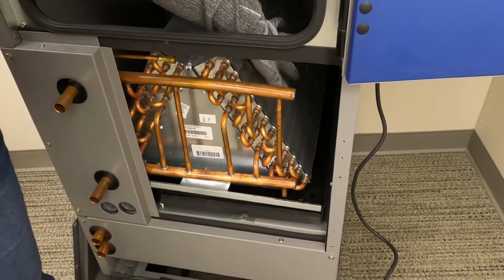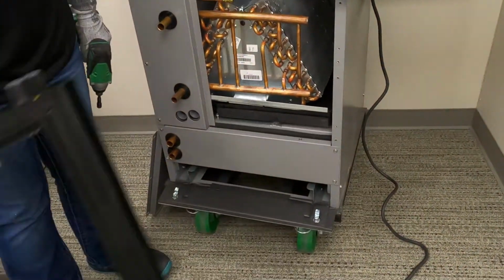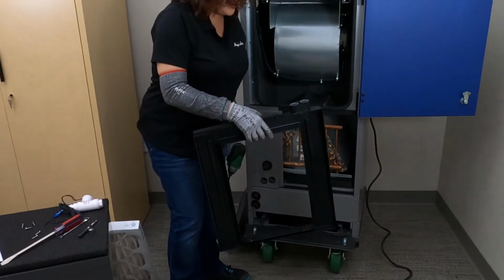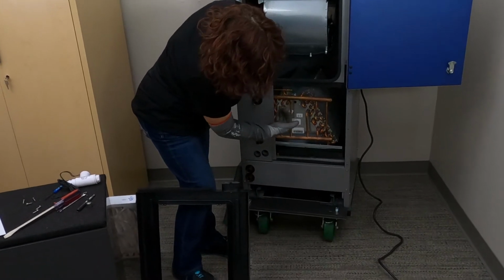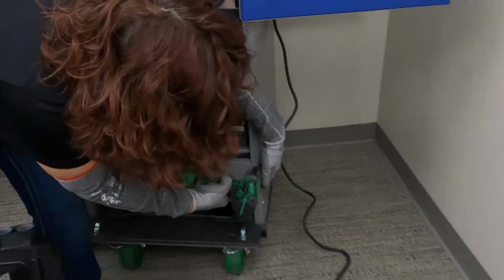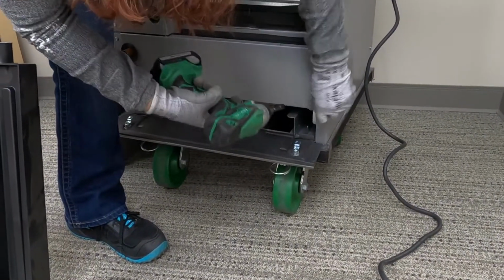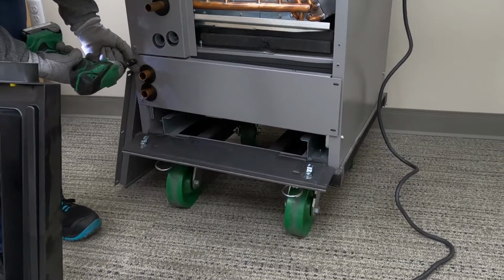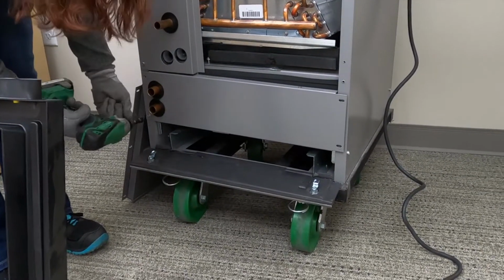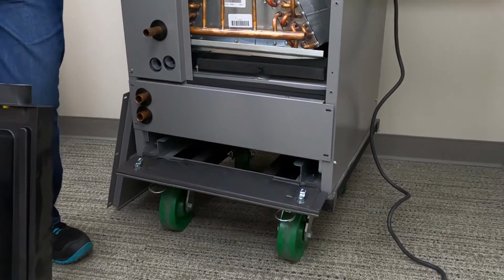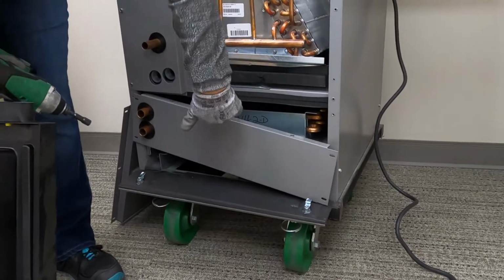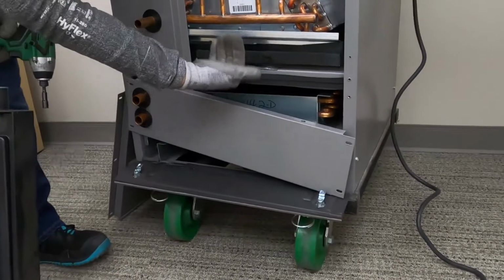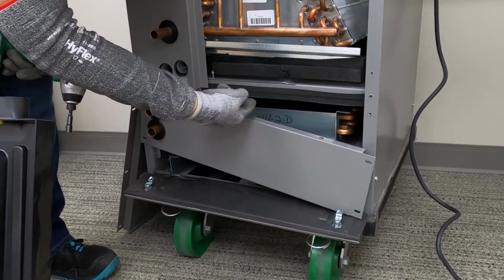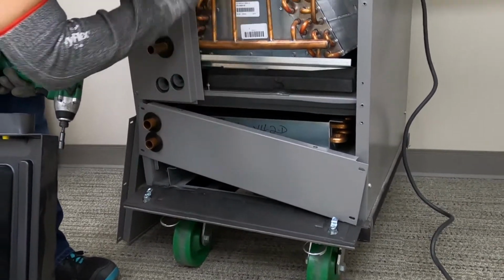All right, you're going to spray on both sides of the coil here, and the bottom has an open section in the drain pan. So there's an opening here where you can spray up on the inside of this A coil. And so when you put a pan here, you don't have to remove the heating coil, but if you will loosen this panel like so, you will have enough that you can go in there and spray up and get in between the heating coil and the cooling coil and up through the drain pan hole and get the bottom side of the cooling coil. And you can also turn around and spray the top of the heating coil, and all this should be cleaned with a non-acidic detergent as needed.